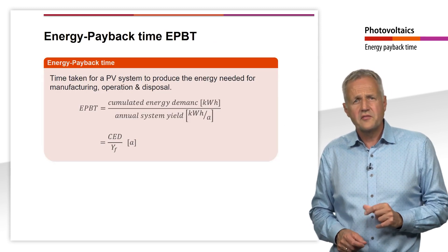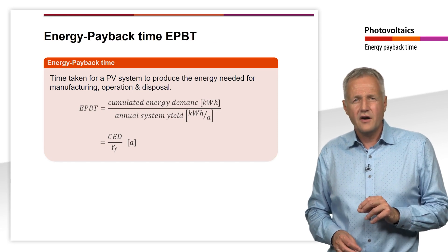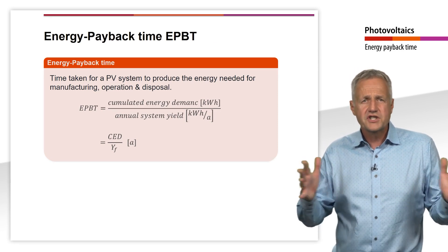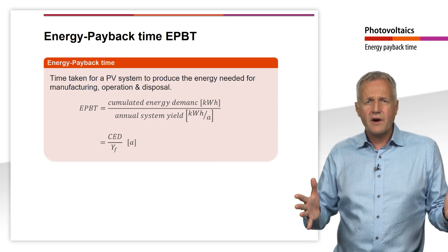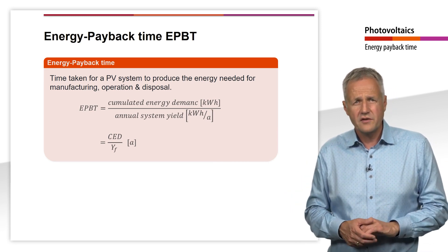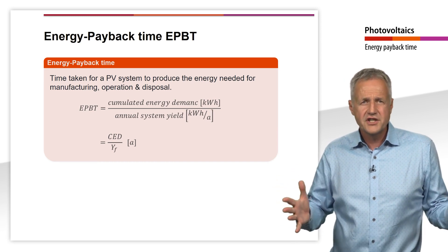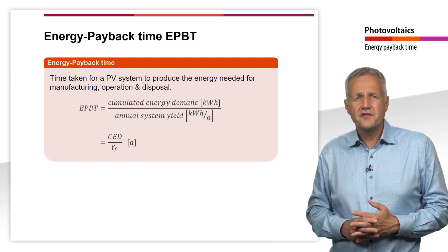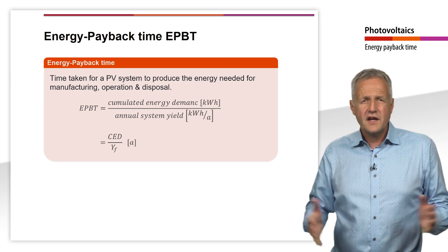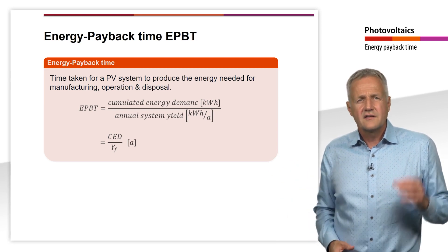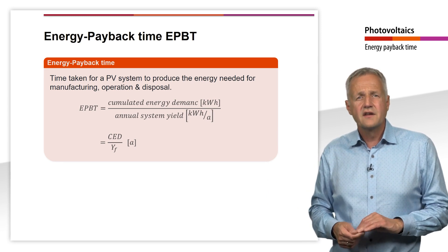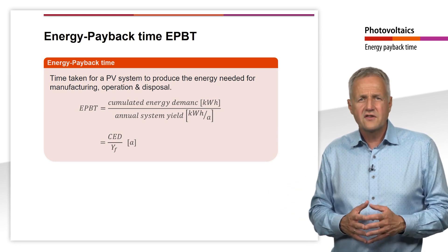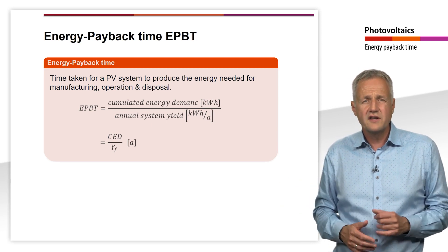A frequently used measure of the environmental impact of a PV system is the energy payback time, E-PBT. The energy payback time is the time in which a PV system has produced the energy required for production, transport, operation and disposal. Mathematically, it corresponds to the ratio of the cumulative energy demand in kWh to the annual yield of the system in kWh per year. The unit of energy payback time is thus years. The greater the annual yield of the plant, the smaller the energy payback time. A small energy payback time means the plant has produced the energy needed for its production, operation and disposal in a shorter time.